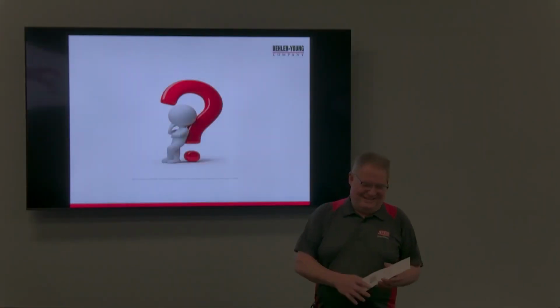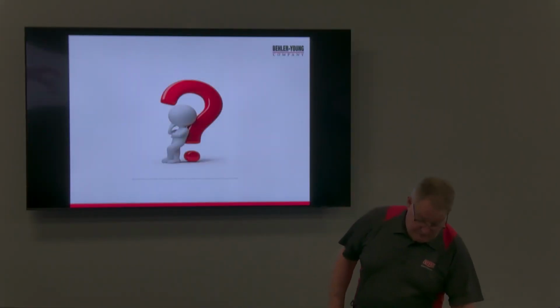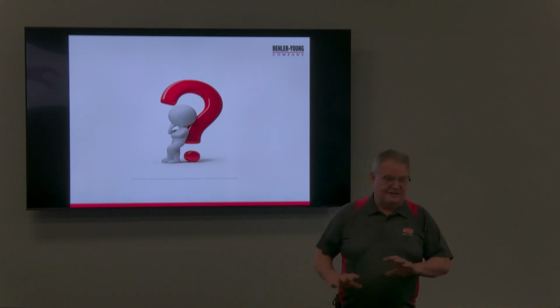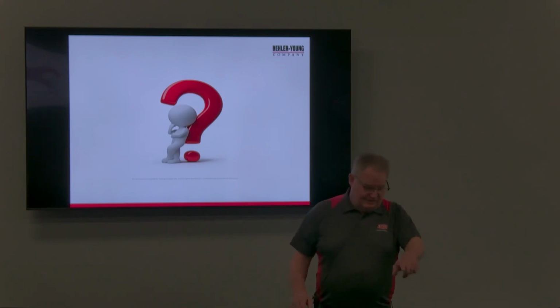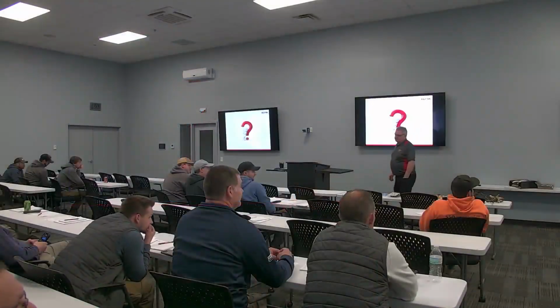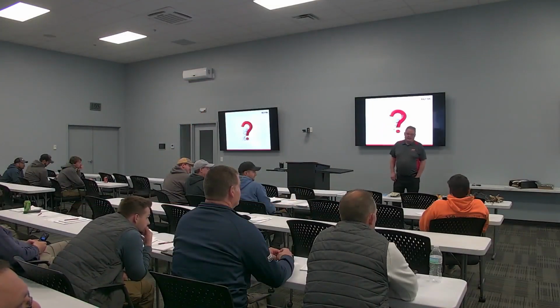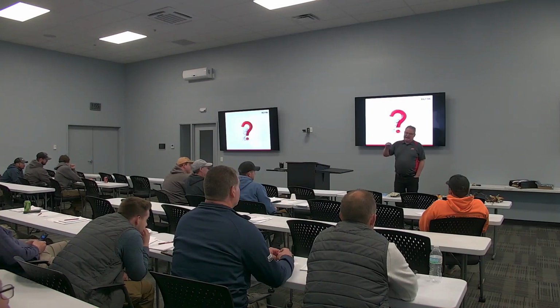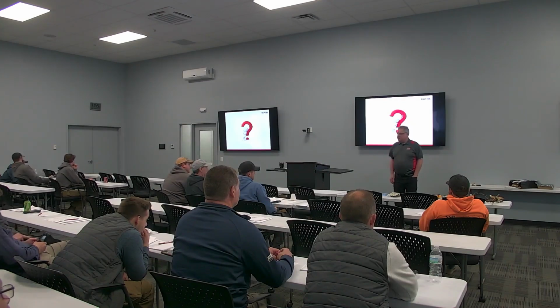Like I said, if you work for me 2 years, analogs, you're not touching a digital for 2 years because you have a PT chart, and you might not even get one with a refrigerant on it. You're gonna have a PT chart in your hand. With the digital gauges, you'll never see that shaking needle. No. And that being said, though, most of your digital gauges, if 454B is not on them, you can probably get them updated. So check with your manufacturer on those.